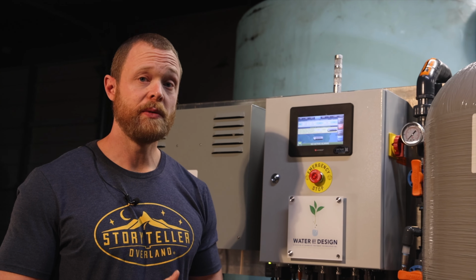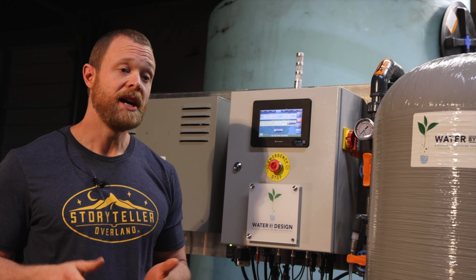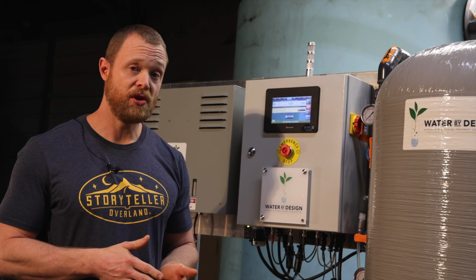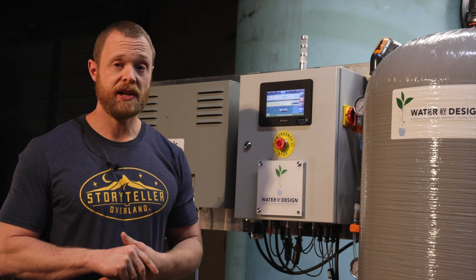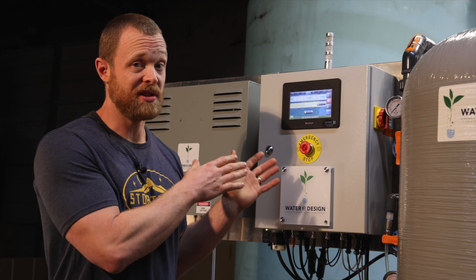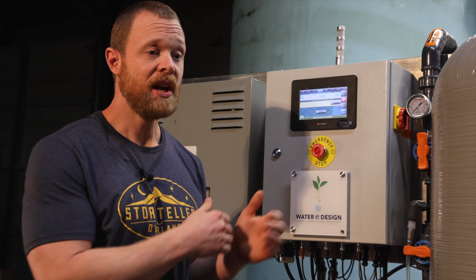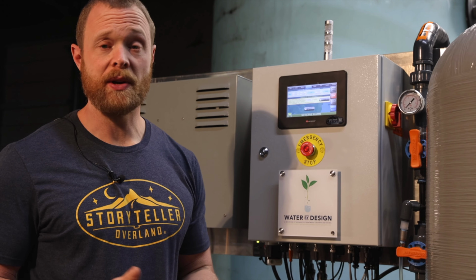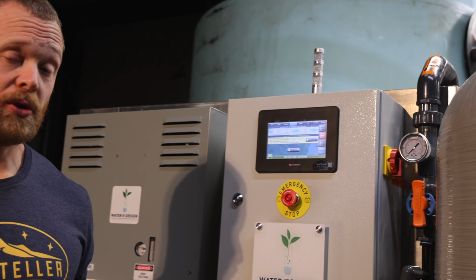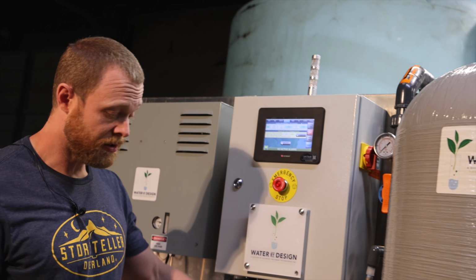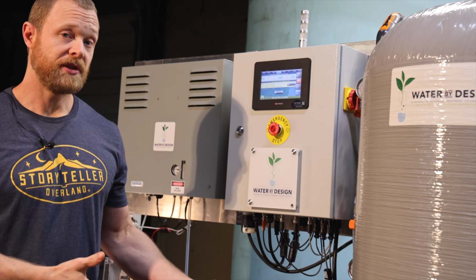But we recommend that you replace that salt bridge about once a year. That's probably a little more frequently than you're going to need to, but if you'll do that once a year, it'll make sure that your calibration is actually right when you go up here and do that. And again, it's a fairly inexpensive thing to do, and it only takes a few minutes, and that's all you have to do. The probe's calibrated, you can reinstall, open up your valves, and start the system again.